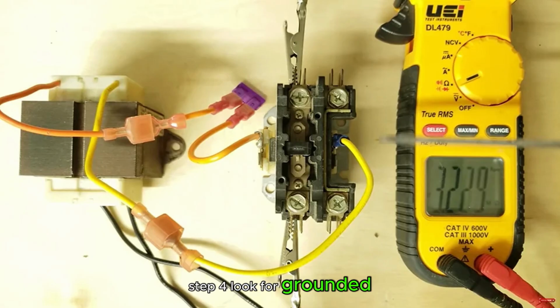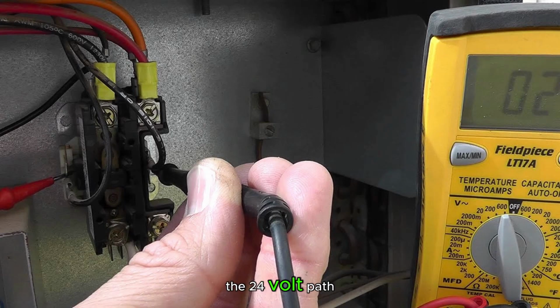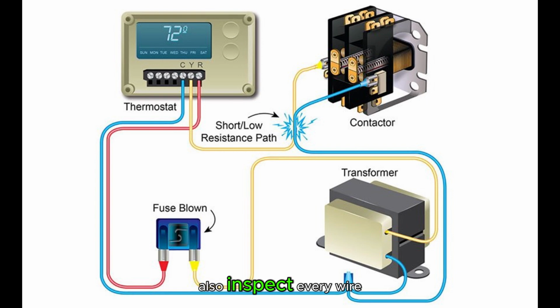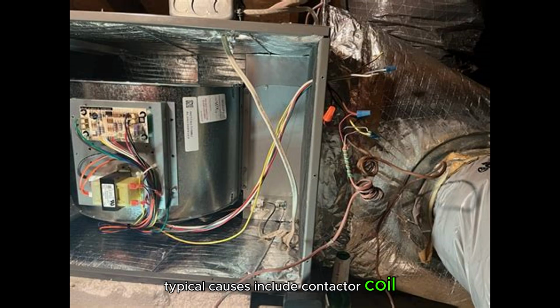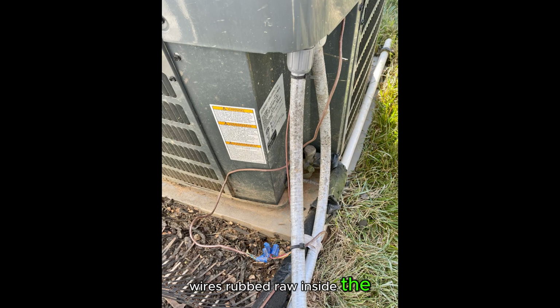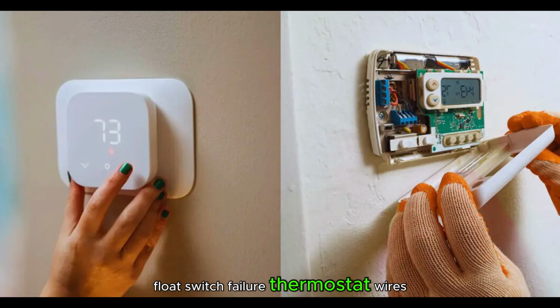Step 4. Look for grounded or shorted components. Check for short circuits in the 24-volt path. Use your meter to test resistance at the contactor coil, relays, safety switches. Also inspect every wire. If a 24-volt wire touches the metal of the machine, even for a second, it will blow the fuse. Typical causes include contactor coil shorted, wires rubbed raw inside the condenser, float switch failure, thermostat wires pinched inside the wall. Be methodical. Disconnect components one by one until the short disappears.